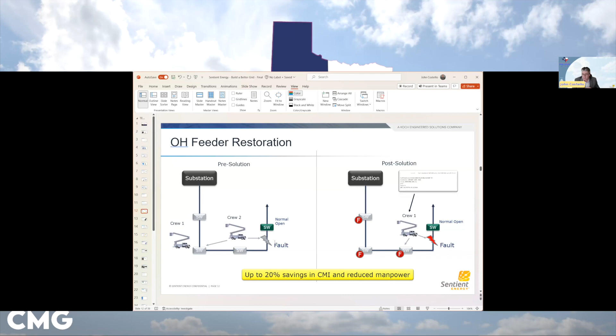So for one particular utility, you can see here that there was a fault, and using sensors, we were able to reduce the inspection distance by 66%. So they were able to go to one specific segment of this feeder to see what the issue was. Our accuracy, we have 90% accuracy of the fault location if you're using more advanced software and circuit models. This particular customer, using our sensors deployed over their system, not 100% penetration, but more on the problematic feeders, was able to save 22.3 million CMI over 2 years.